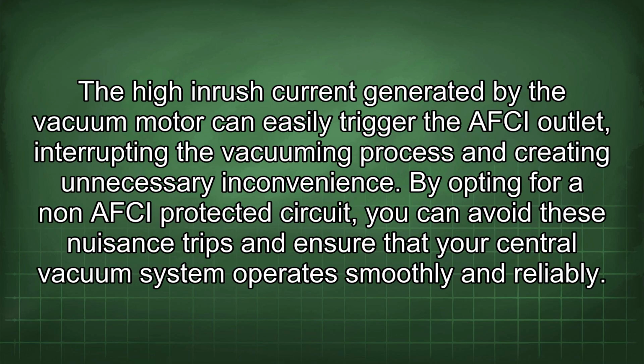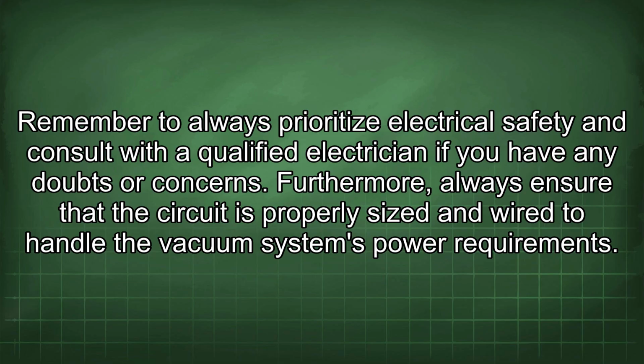The high inrush current generated by the vacuum motor can easily trigger the AFCI outlet, interrupting the vacuuming process and creating unnecessary inconvenience. By opting for a non-AFCI protected circuit, you can avoid these nuisance trips and ensure that your central vacuum system operates smoothly and reliably. Remember to always prioritize electrical safety and consult with a qualified electrician if you have any doubts or concerns. Furthermore, always ensure that the circuit is properly sized and wired to handle the vacuum system's power requirements.